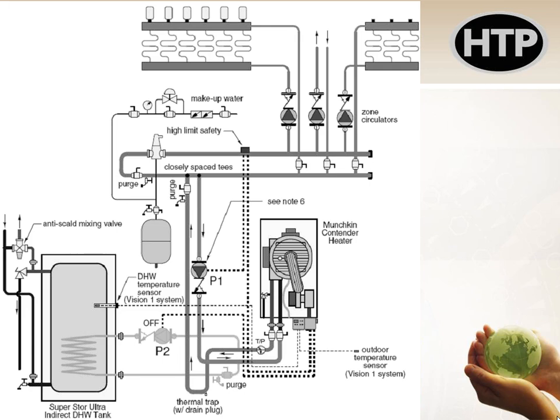All right, so here's a typical drawing of a condensing boiler, and I'm talking specifically about HTP boilers now, and most stainless steel heat exchanger boilers from most manufacturers. And then there might be some exceptions to that, and I'll point those out as we go. But for the most part, this is how you're going to be piping these things. So I'm hoping that you guys can see my mouse moving around here on the screen. On the right-hand side here is a condensing boiler, stainless steel heat exchanger.